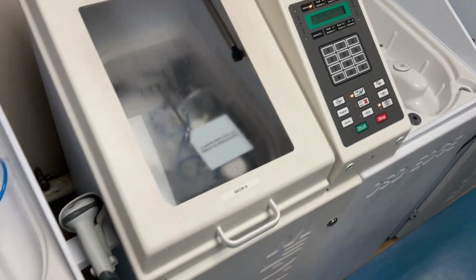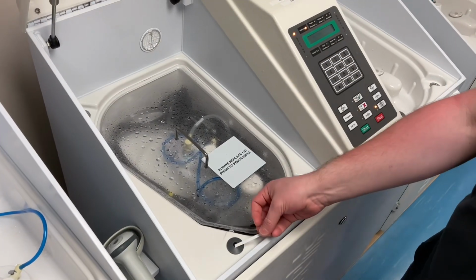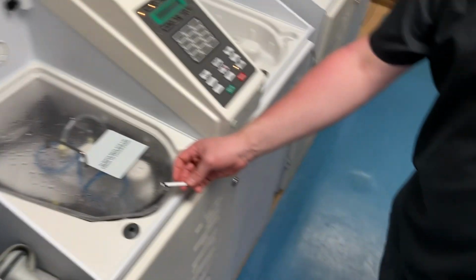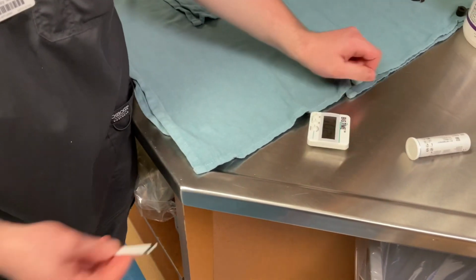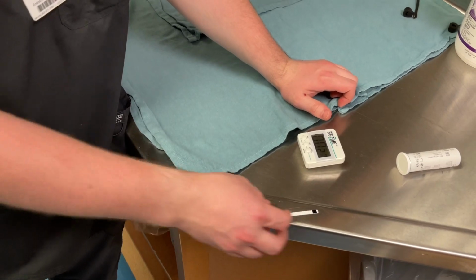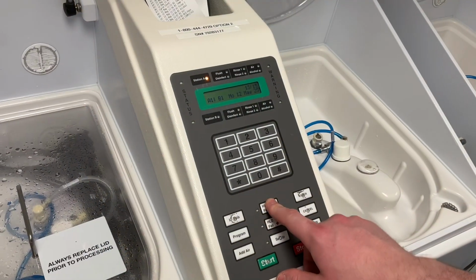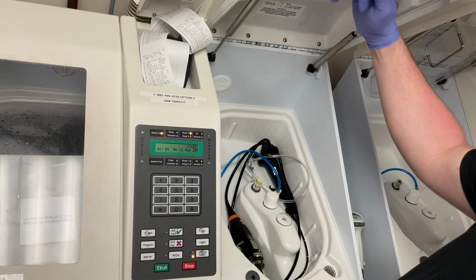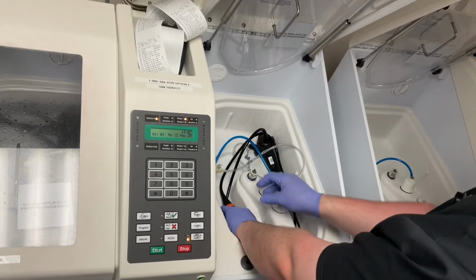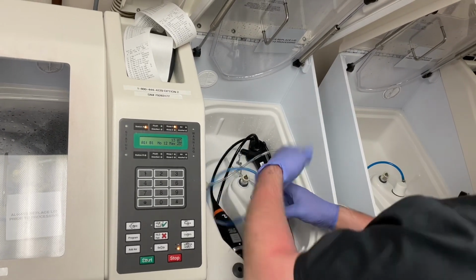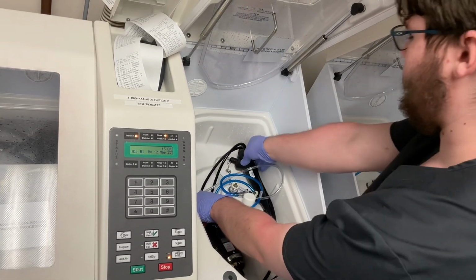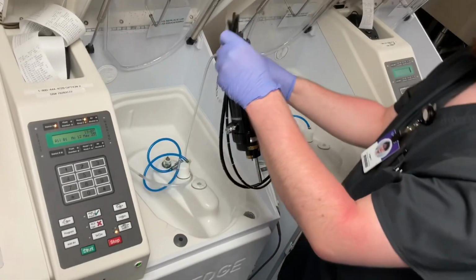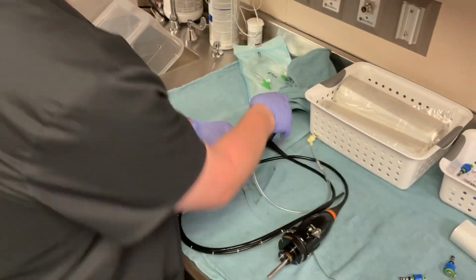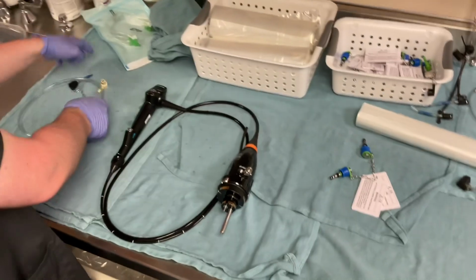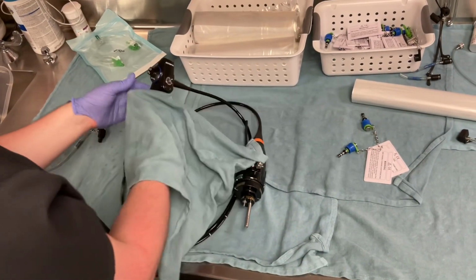Once the process has been completed for high-level disinfectant, we will need to check for rapicide concentration by doing the dipstick, letting it sit for 30 seconds, and confirming that the high-level disinfectant has passed. We can then take the scope out of the Medivator and proceed to dry all exteriors of the scope. Verify that nothing has become detached during the cleaning process within the Medivator. If you notice that the hookup has become detached, you will need to reprocess the scope within the Medivator.